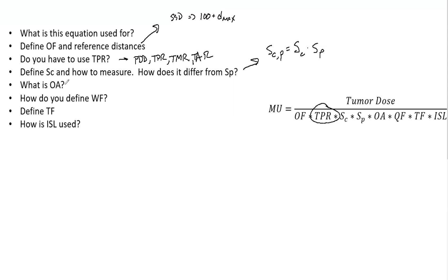This is needed because the beam is never perfectly flat, right? Even the beams that we really like, they may be somewhat off. They're never perfectly flat. You have separate data for open and wedged fields, and you just reference it to come up with your off axis ratio. If your calc point isn't on central axis. If it is, that is just one.